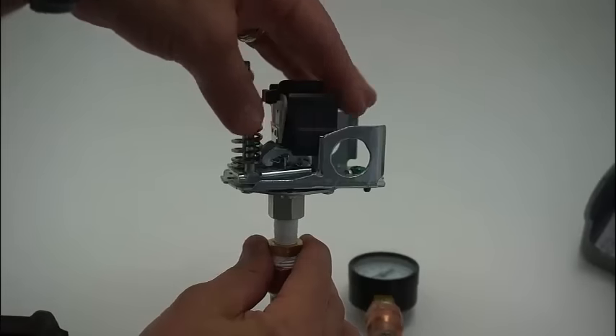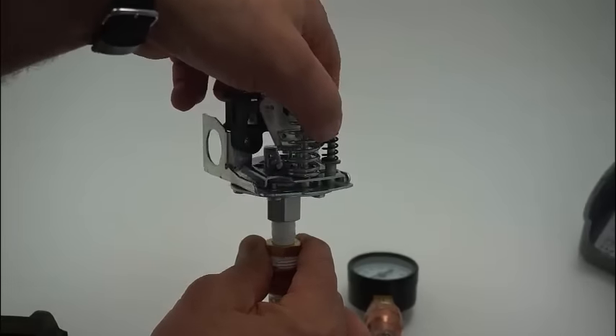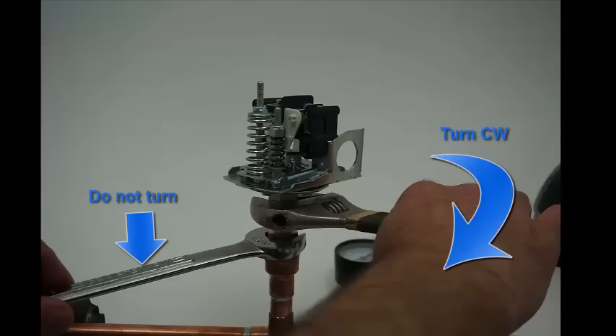Hand tighten the 9013 FSG Pressure Switch by rotating it in the clockwise direction. Use a crescent or box-end wrench to tighten the pressure switch to the pipe NPT threads. Be sure to use a wrench on the pipe fitting to provide support and keep it from turning.